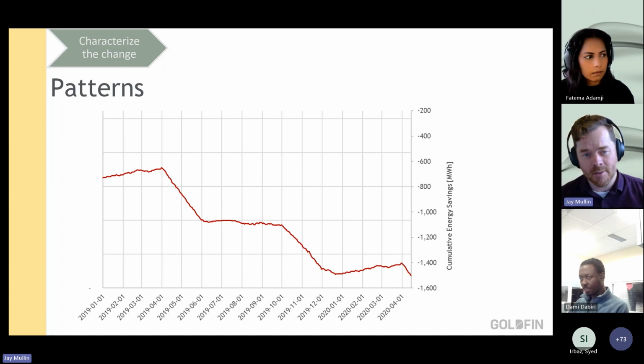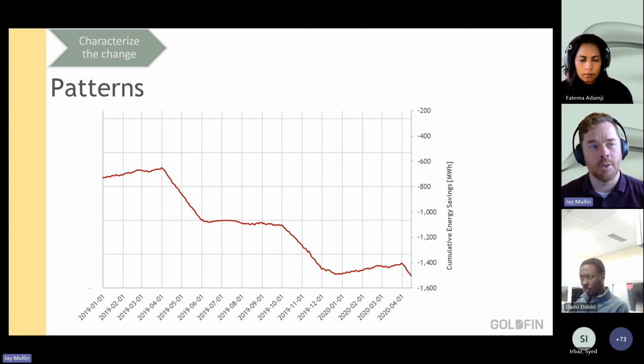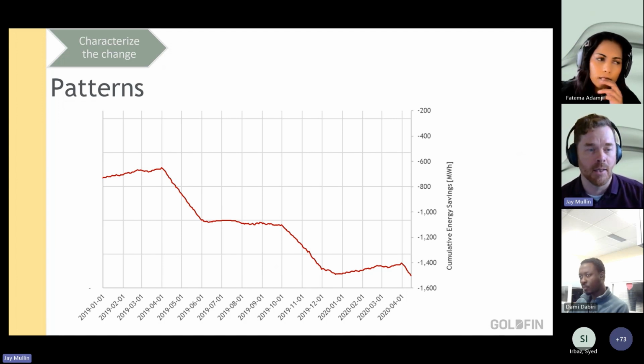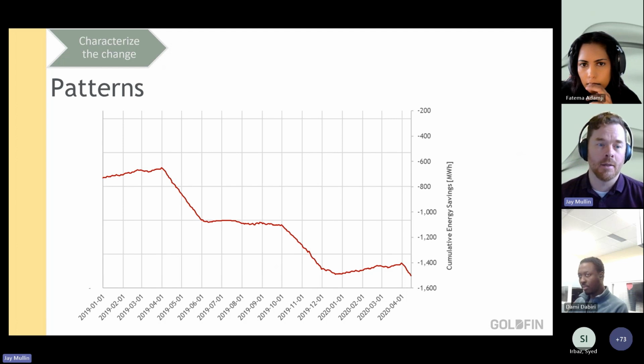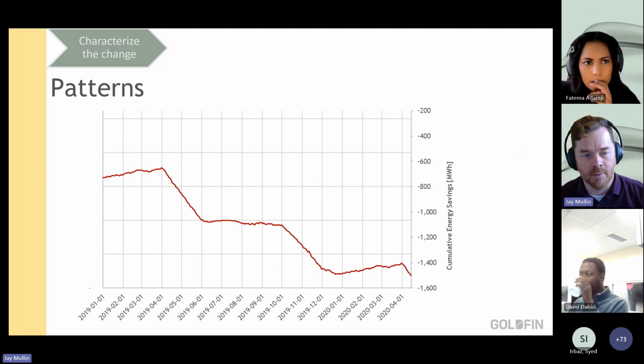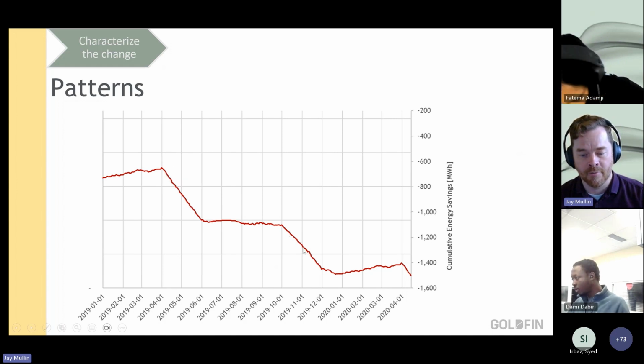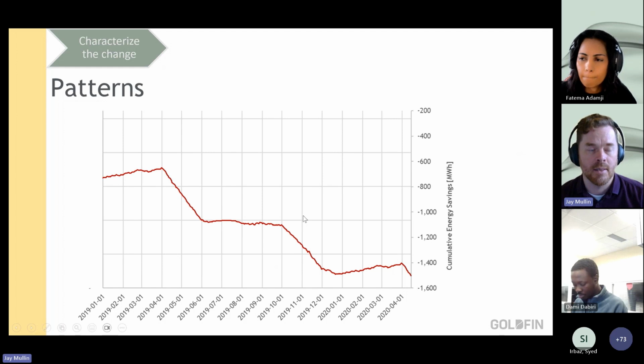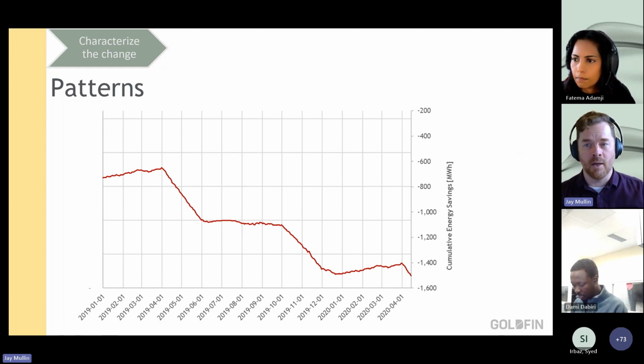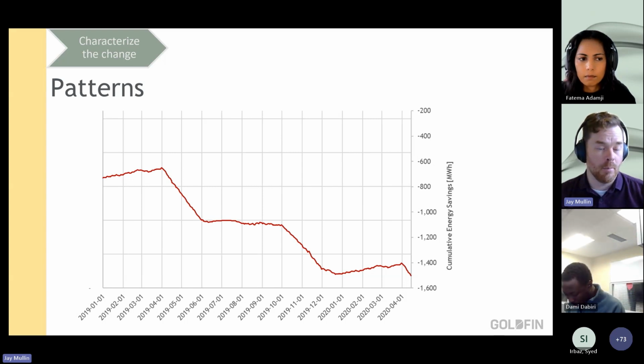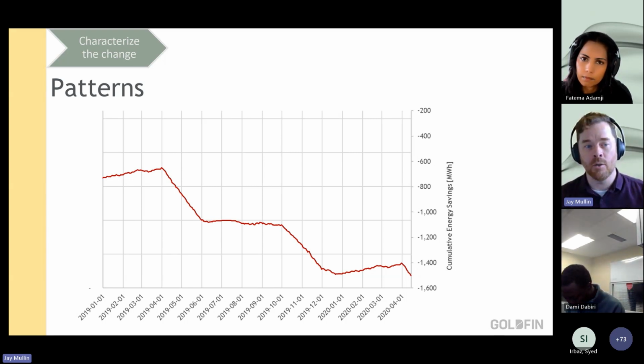You can also look for seasonal patterns that can indicate the change occurred in a system that operates periodically, or because of conditions that occur periodically. In this example, we are having these negative savings, and they seem to be occurring during the spring and the fall, while maintaining a pretty flat CUSUM during the winter and summer seasons. So it's like, okay, what's different about spring and fall than these other periods? It could be a potential issue where we're having simultaneous heating and cooling happening. We don't know for sure - these are just sort of clues that lead us to guesses, hypotheses. It's not going to tell us, but they're the clues on this.